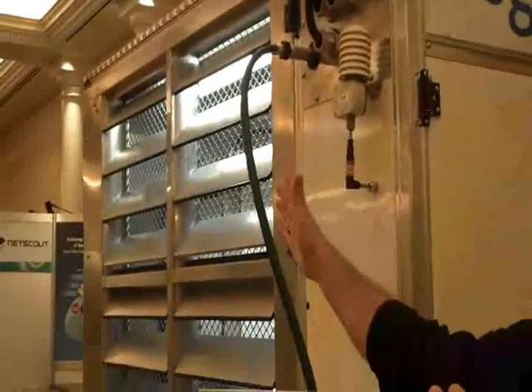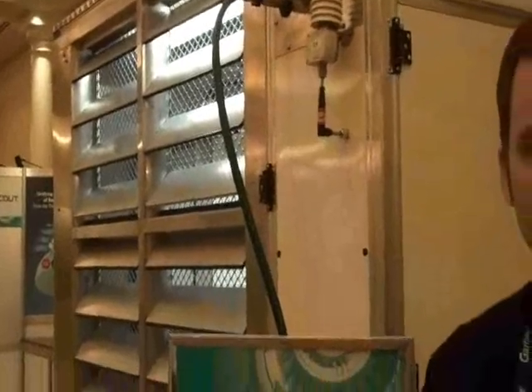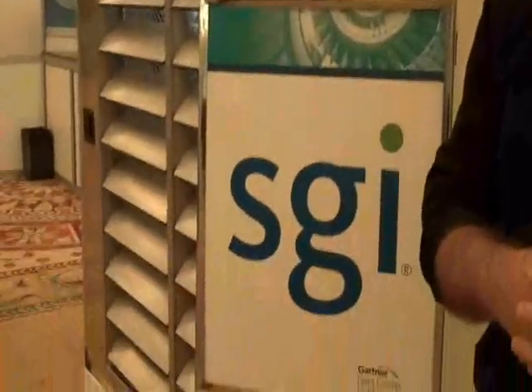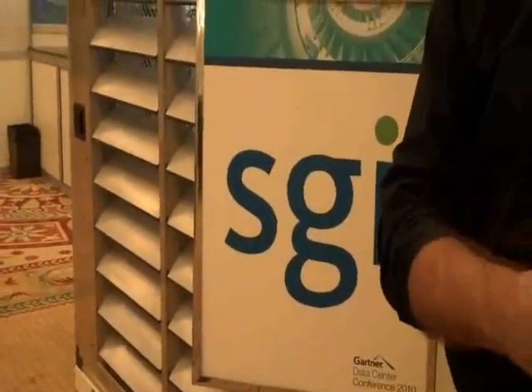What we've done with this particular modular data center is we've taken what normally is in an ISO shipping container and turned it sideways. In a typical ISO shipping container, you have issues around space for the operational people, for maintenance people, et cetera. So we've turned the racks sideways and allowed them to expand in that direction. This is a four-rack unit. It's a little bit smaller than the actual production unit, but it expands out to 16 racks.